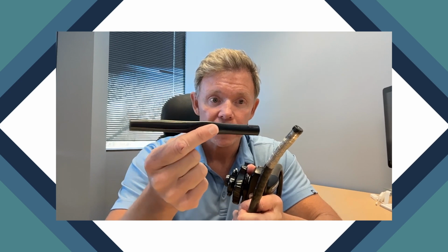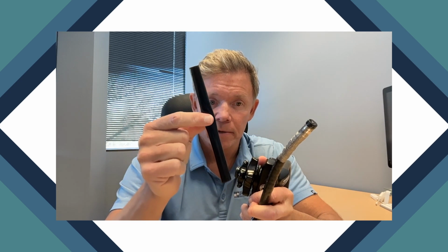Okay. And one of the reasons, Frank, tell them why, the angulation and where it comes from, because of passing the sharp instrument when the scope is fully angulated. Yeah. So there are many reasons why you can get a leak in this outer sheath. It could be a sharp fingernail. It could be the scope was put in the sink with some other sharp instruments. It could be this tip dragged across the countertop or hit the floor. There are a lot of different ways that you can get a leak in this outer sheath.